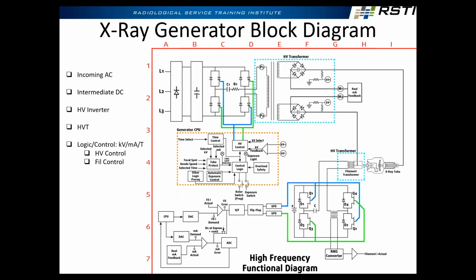It's a high frequency inverter. It's taking IGBTs and chopping them up. So there's a signal coming from the computer saying, I want you to fire these two, then these two, then these two, then these two. And what's happening is I'm passing DC through the transformer to make it look like AC. And again, the whole purpose of this is that I can more quickly and accurately control the DC than I can the AC. So this is really what's producing my kV, my kilovolts. I'm firing this inverter to give me a certain voltage, but only a fraction of it.